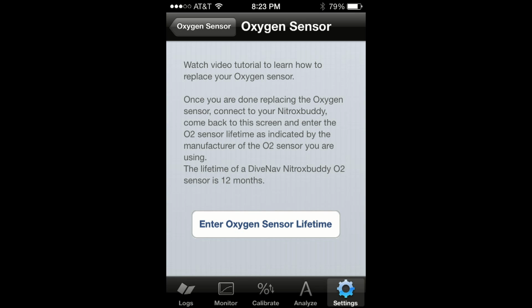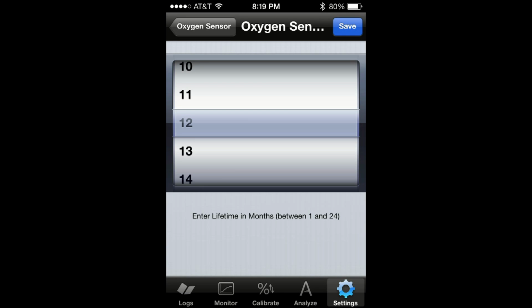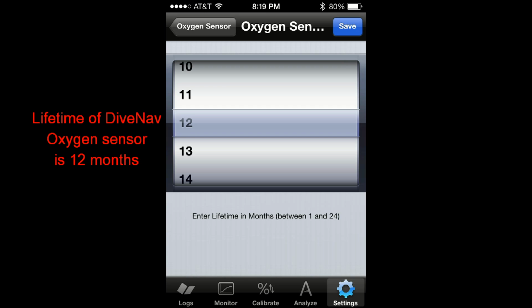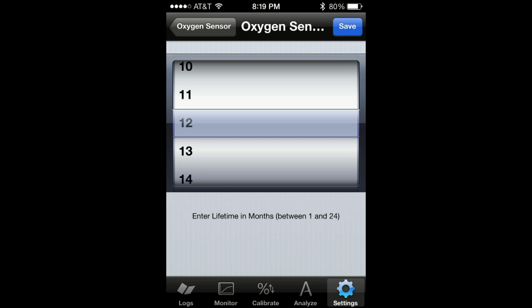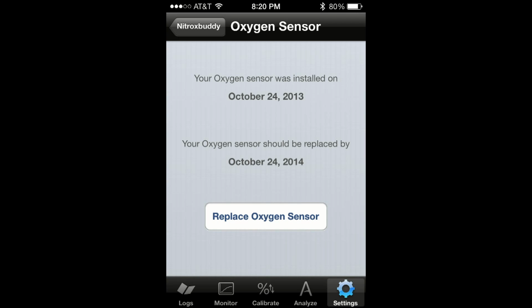Then tap on Enter Oxygen Sensor Lifetime and enter value in months. Please check with the manufacturer of the oxygen sensor you're planning to use for its lifetime. The lifetime of our Nitroxbuddy oxygen sensor is 12 months. Since you just replaced the oxygen sensor, make sure you recalibrate your Nitroxbuddy before using it.